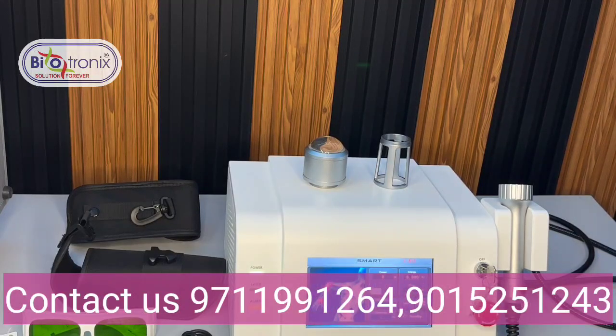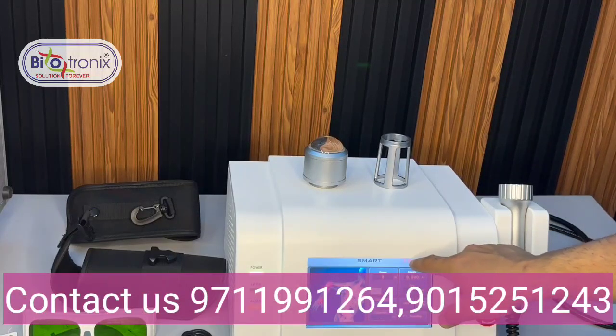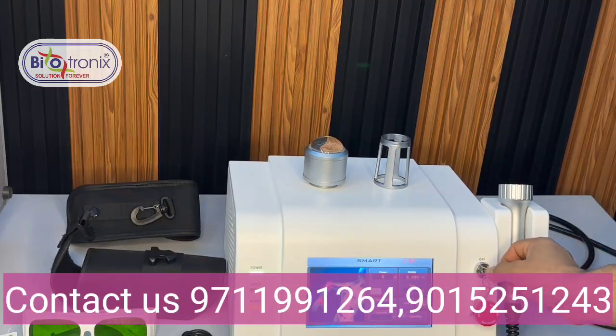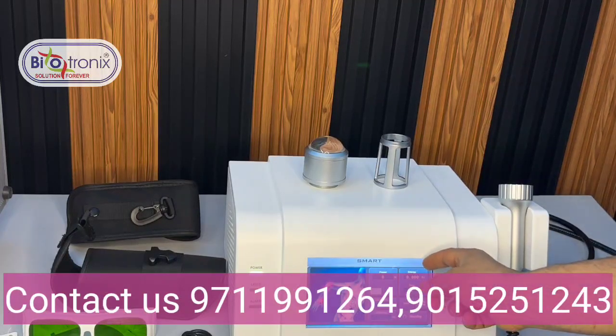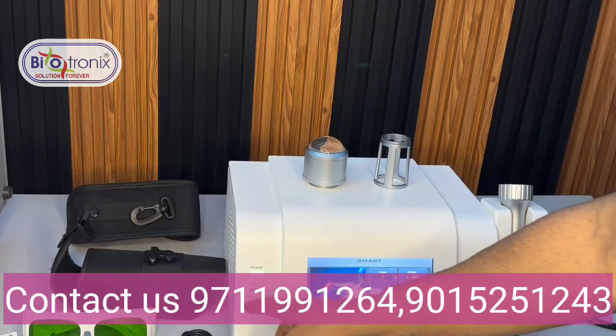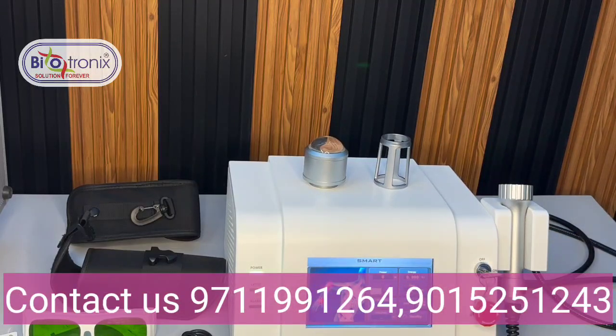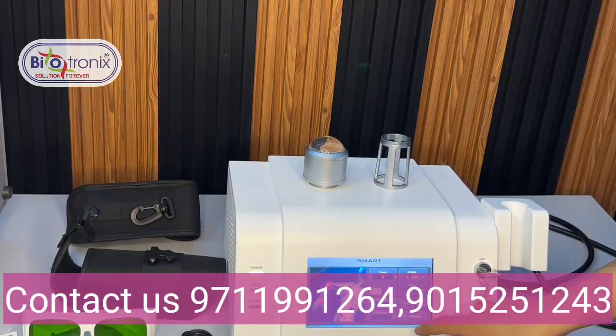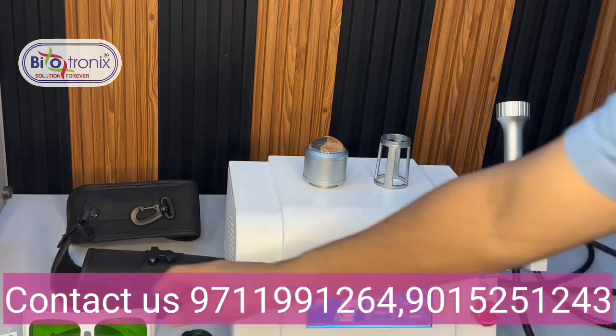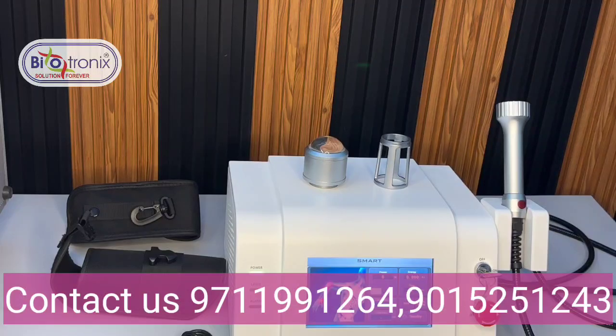Select the confirm. Now you can see the alarm button is glowing on the screen, and you can see the word E key. So this is the key. When you rotate the key from off to on, that indication will be gone, and that alarm indication will also go. So now the device is ready to use. And when I put it in standby, like I take the probe out, before showing you the demo, I need to wear the protection glasses. Always wear the protection glasses before using the laser.